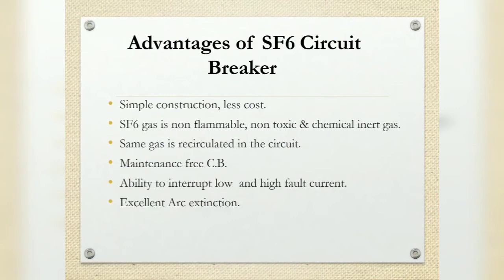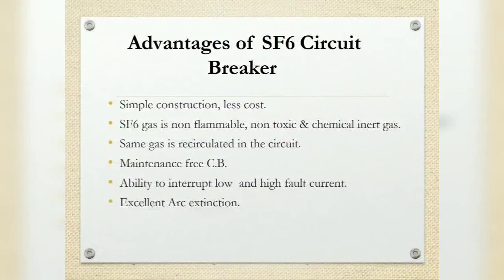There is no reduction in electric strength because no carbon particles are formed during arcing. It requires less maintenance and no costly compressed air system as is required in the air blast circuit breaker. So here we just require a reservoir to store SF6 gas.